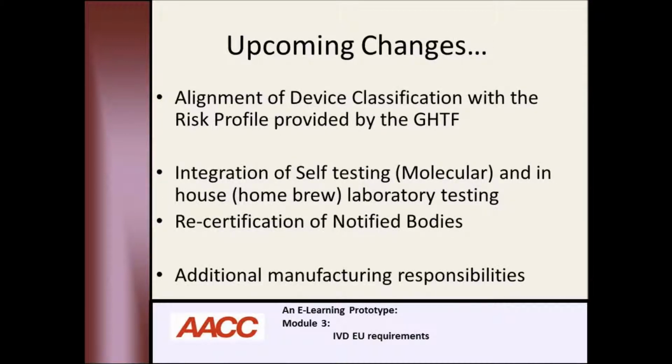The IVDD is in the midst of a major revision process. While nothing is yet set in stone, expected changes include a revision to the process for device classification, integration of self-testing with a special emphasis on molecular testing into the regulation, acknowledgement of in-house testing, referred to as LDTs in the US, recertification of all notified bodies by the appropriate competent authorities, and additional manufacturing responsibilities. While some of these points may yet still evolve, there is no doubt that significant change will occur in the next few years.